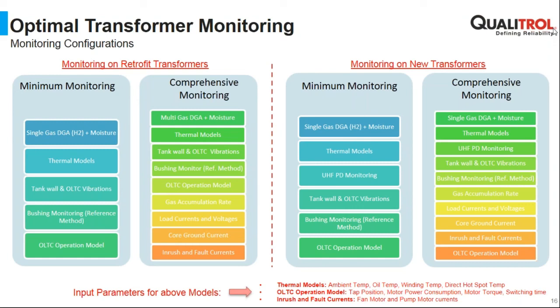Okay. Is there any system that can detect the quantity of corrosive sulfur and the impact it has on windings if the transformer oil is found to have corrosive sulfur in it? Well, that's a whole discussion in itself. The assumption of the industry is that corrosive sulfur is kind of a topic of the past, but obviously if you look at the works which are done at CIGRE, that seems not to be 100% the reality.